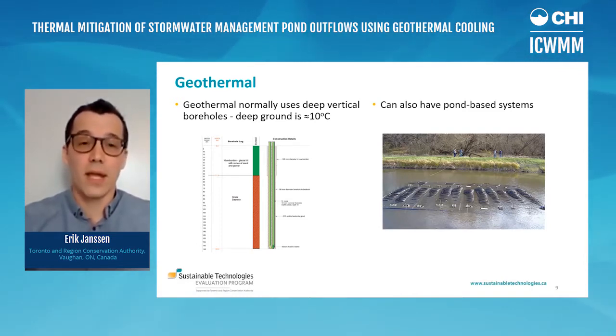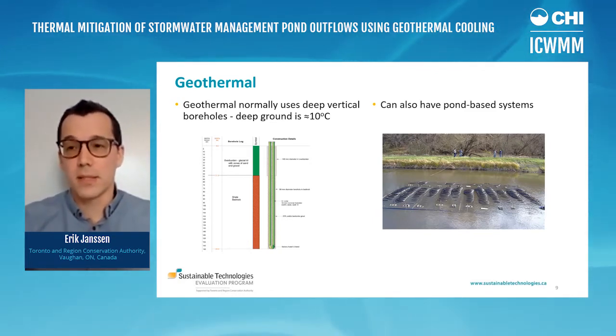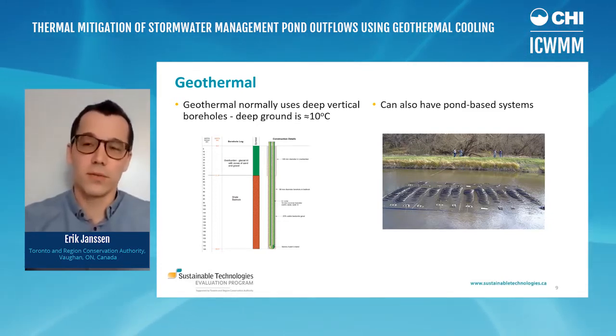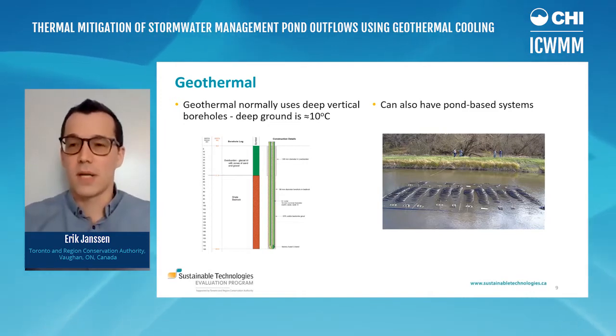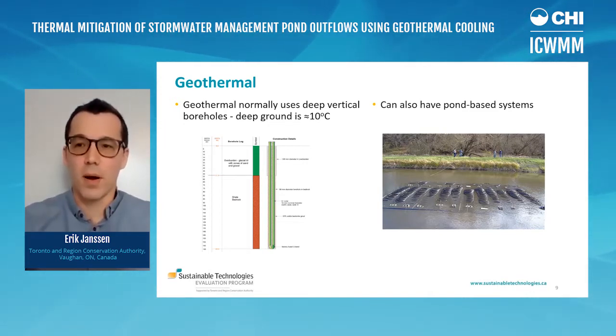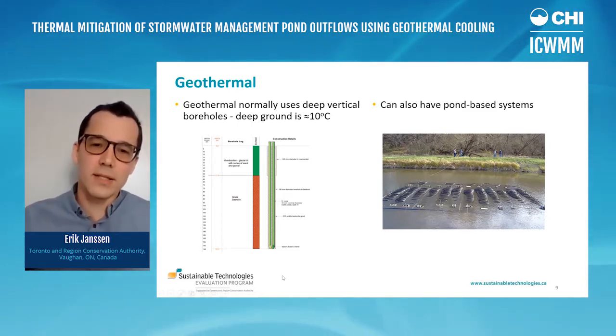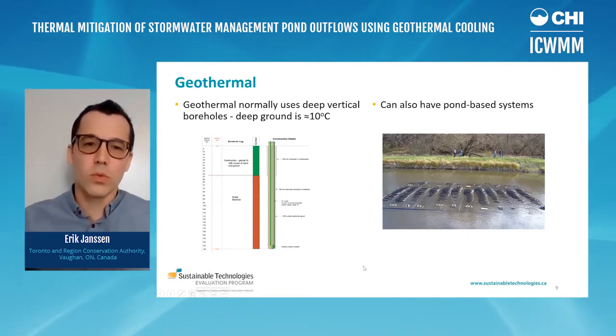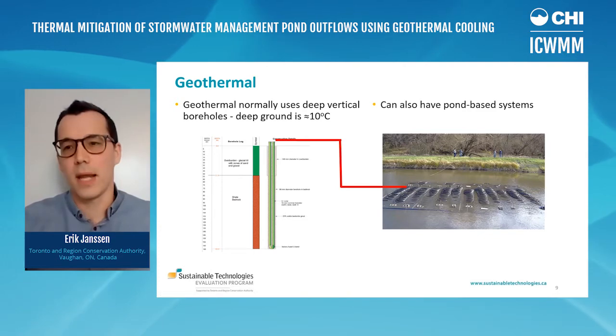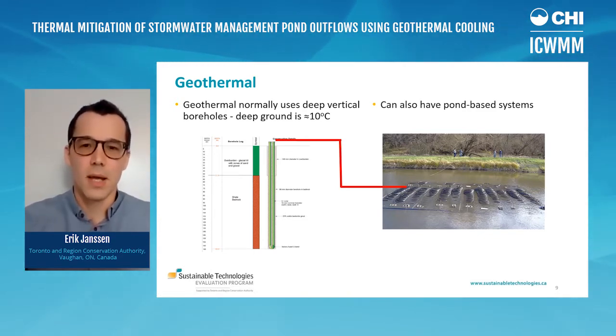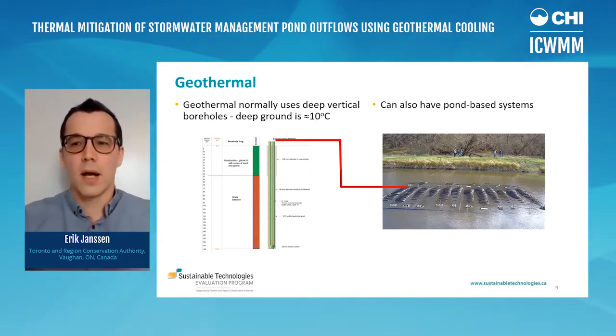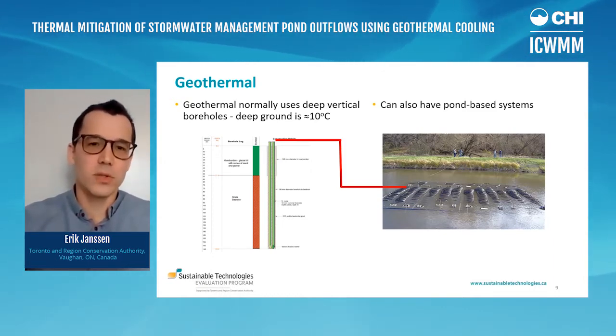Now, if you combine this with a heat pump, you get a really energy efficient heating and cooling system for a building. What's also possible is pond-based systems. We have one of these in downtown Toronto that does a lot of the cooling for the downtown core. Same basic concept. We have a network of piping. In this case, it's sunk to the bottom of a pond. A heat transfer fluid flows through this network of piping, and then you get heat exchange with the pond, either heating or cooling the fluid, depending on the temperature difference. The insight that my colleagues over at Step Water had was, what if we connected a deep vertical borehole to something like a pond-based geothermal system to cool a pond? We're not talking about cooling the whole pond, just the outflows, but you could see how we could use these deep ground temperatures potentially to cool the outflows that are coming from the pond.